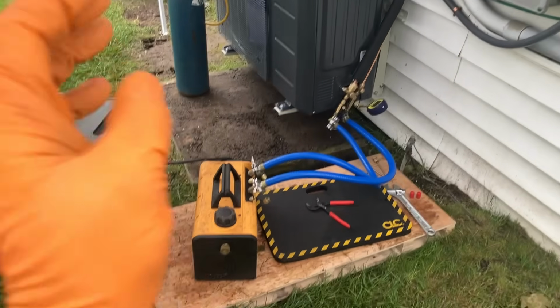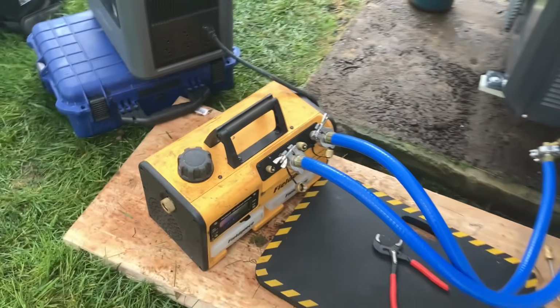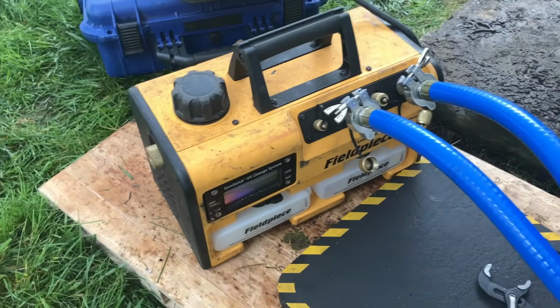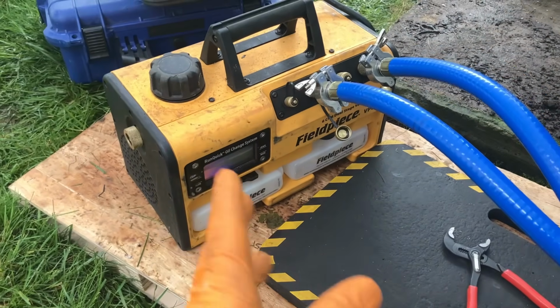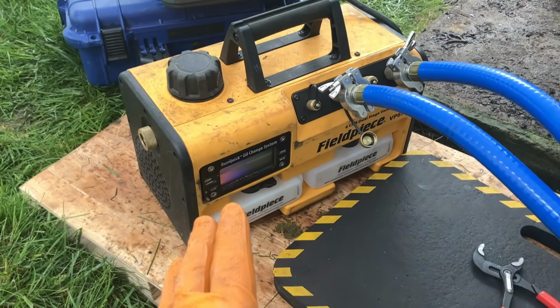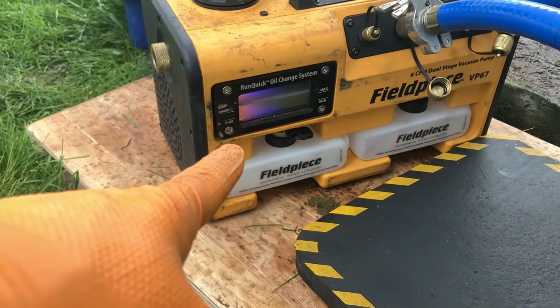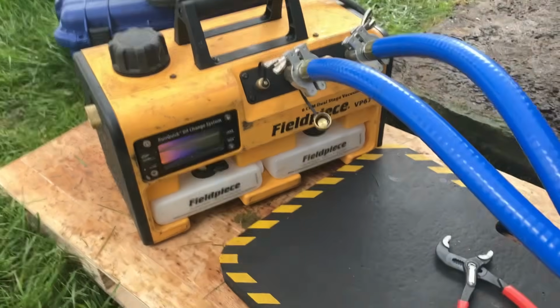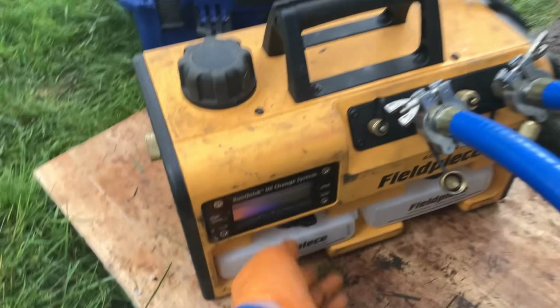So right now we're using a vacuum, I'm using the Fieldpiece. This is the VP67, a dual stage 6 CFM vacuum pump. I like the Fieldpiece vacuum pump because I can change the oil on the fly, just like that. I'm going to show you right now because I haven't changed it all season.